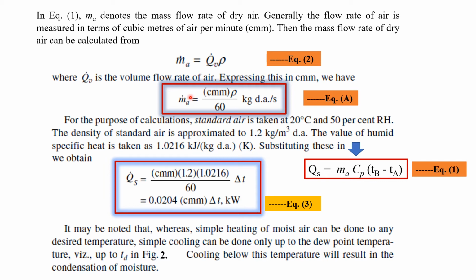Of course, the same quantity by weight of air is leaving the unit as is entering, but the CFM or CMM is greater. This variation in volume can lead to misunderstanding and error, such as selection of the wrong size equipment unless clearly specified. Problems can be avoided by always indicating the temperature and pressure at which the CFM or CMM is specified. However, when rating the capacity of equipment such as fans, coils, and air handling units, manufacturers do not know the temperature and pressure conditions that each user will apply. In order to avoid misunderstandings, the CFM or CMM of the equipment is often expressed at standard air conditions.